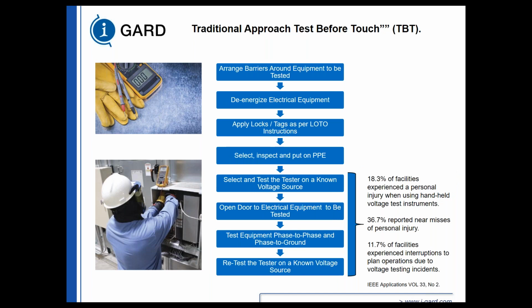So what we find is, after we put on the PPE, this is when most people get hurt. After the PPE is put on, 18.3% of facilities experience personal injury when using handheld voltage test instruments. 36.7% reported near misses or injury. 11.7% of facilities experience interruption in planned operations due to voltage test incidents. This is after we put on the PPE.